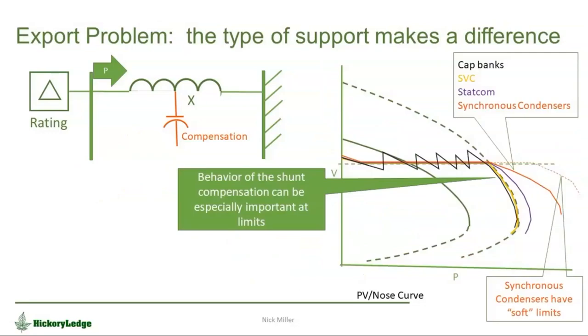But as I push the system out, it gets progressively more brittle. And on this slide, you see the variations in the different kinds of support. So synchronous condensers don't have hard limits. They are slower, but they don't have hard limits on their current delivery. So they tend not to bang into limits, as this drawing suggests, between shunt banks, SVC, and STATCOMs, all of which have hard limits. So a condenser is going to be, in some regards, a better mannered compensation than the other ones. And it also contributes short circuit strength to make the inverters back upstream behave better. But it's not as close, so it doesn't do as much good.